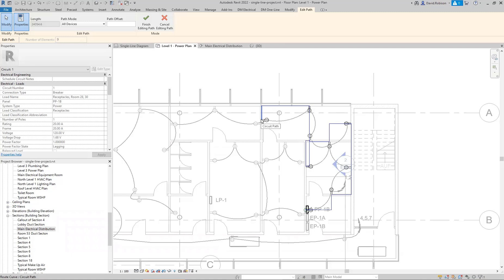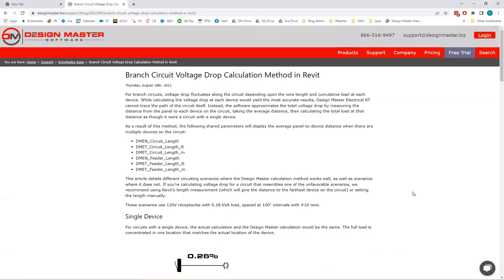Revit's calculated length puts the entire load at the very end of the run, which is not necessarily the most accurate way to do a voltage drop calculation. You need to put your engineering hat on and figure out how you want to do the calculation. There's a knowledge base article that walks through how the average distance approach impacts the final voltage drop values.